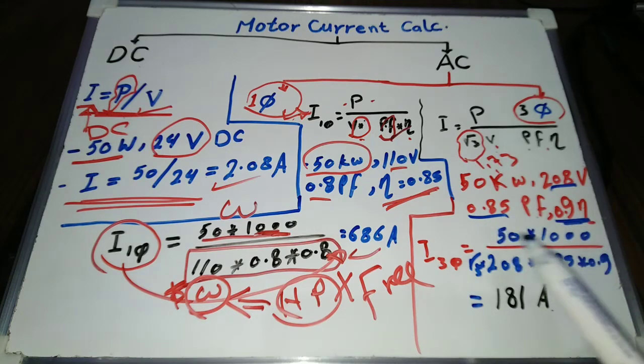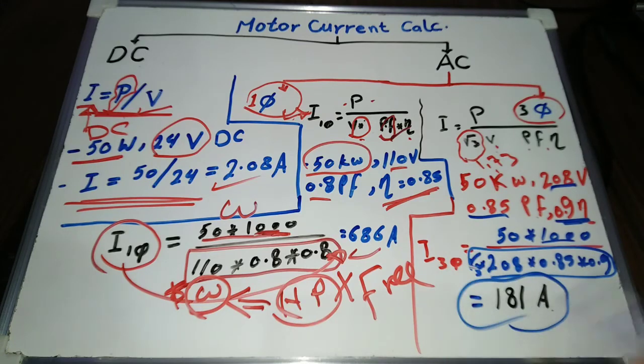Motor current equals 50,000 divided by 275.27, equals 181 amps. Note that three phase motors' power factor and efficiency are usually greater than single phase motors.